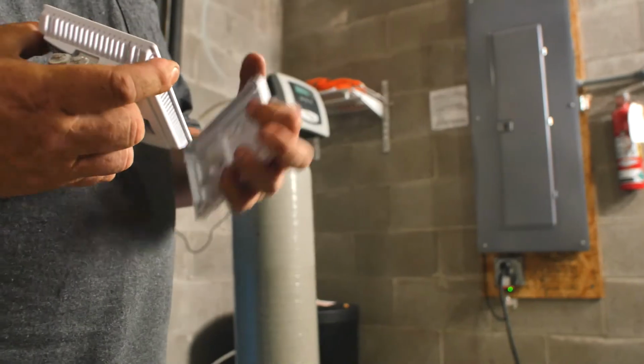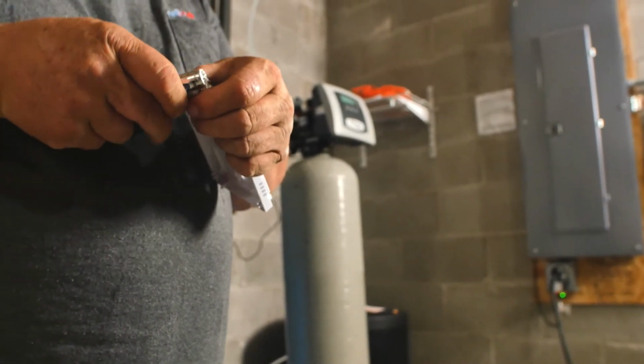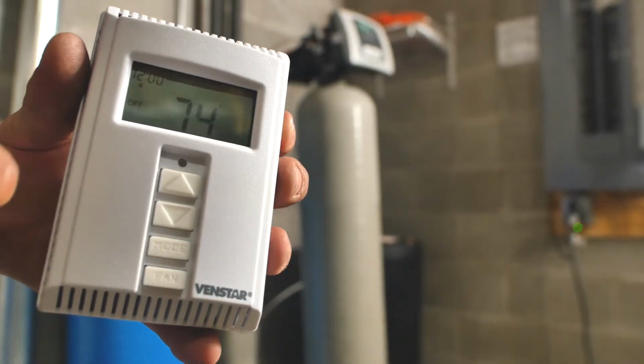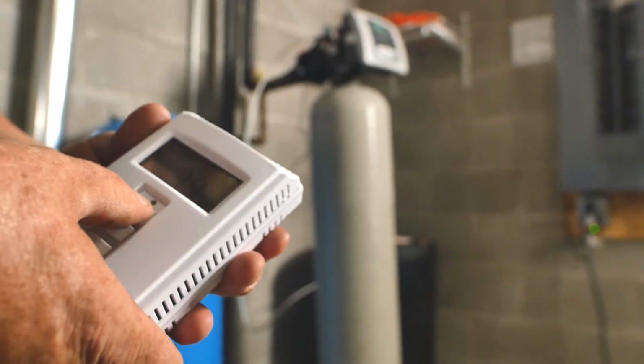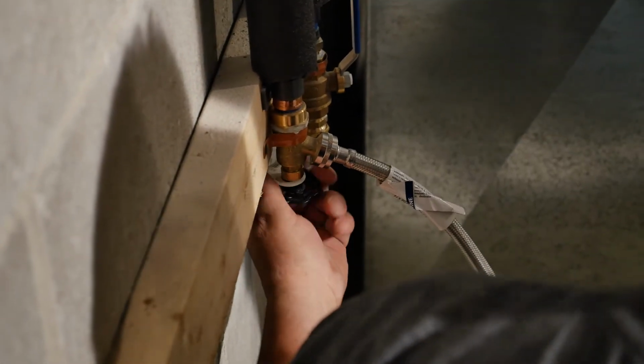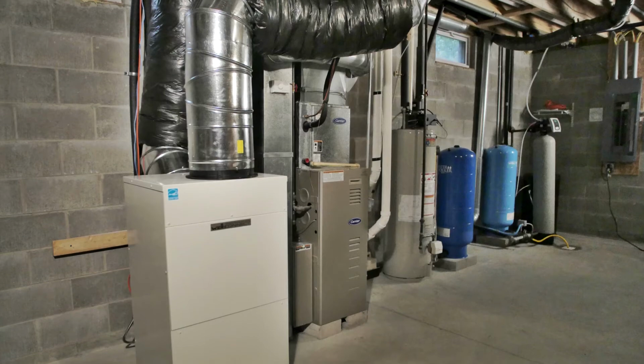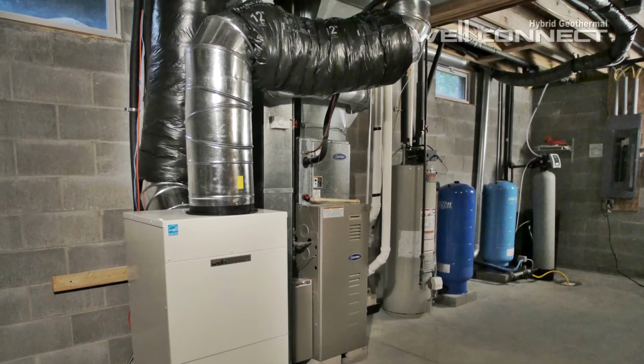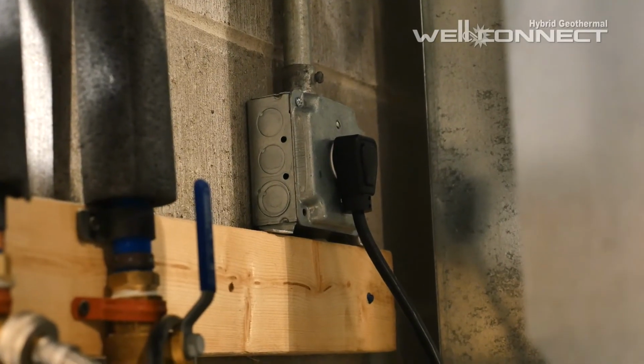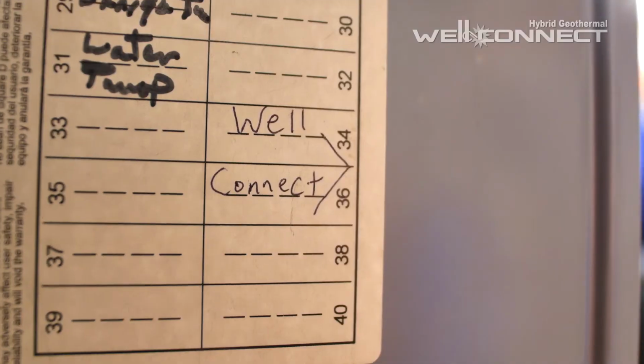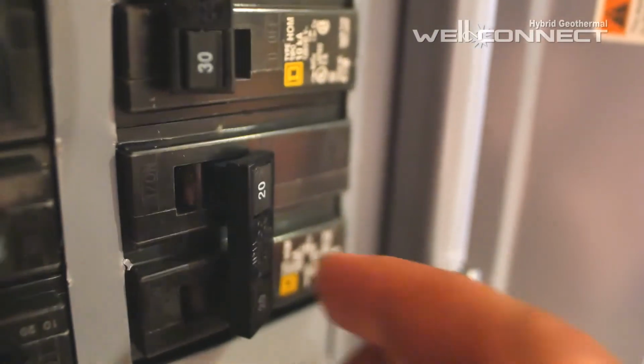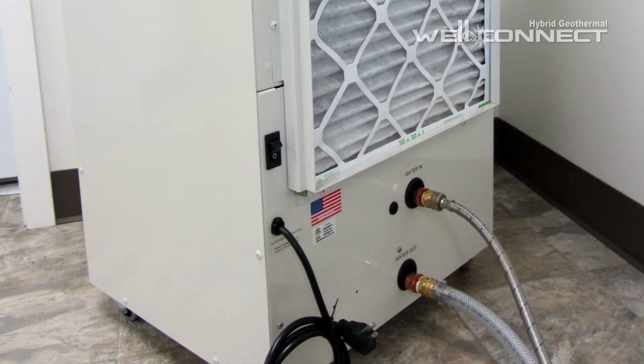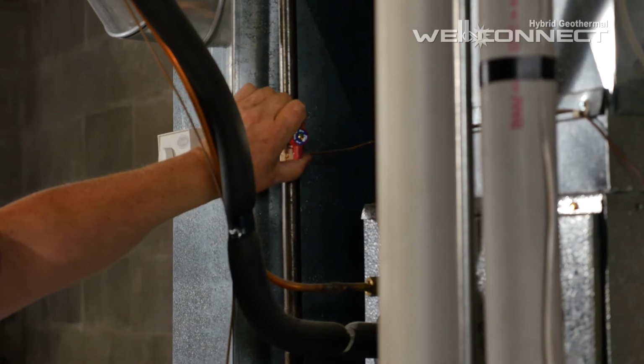To prepare for system startup, first install the 2 AA batteries found in the box with the wireless thermostat and set the thermostat mode to the off setting. Next, open all valves on the water supply and water discharge piping, checking for any obvious leaks. Make sure the Well Connect power cord is plugged into its receptacle and turn on the circuit breaker in the main service panel. Note that there is also a power on-off switch on the rear side of the Well Connect. Make sure this switch is on. Remember to open the gas valve and turn the furnace power switch back on.